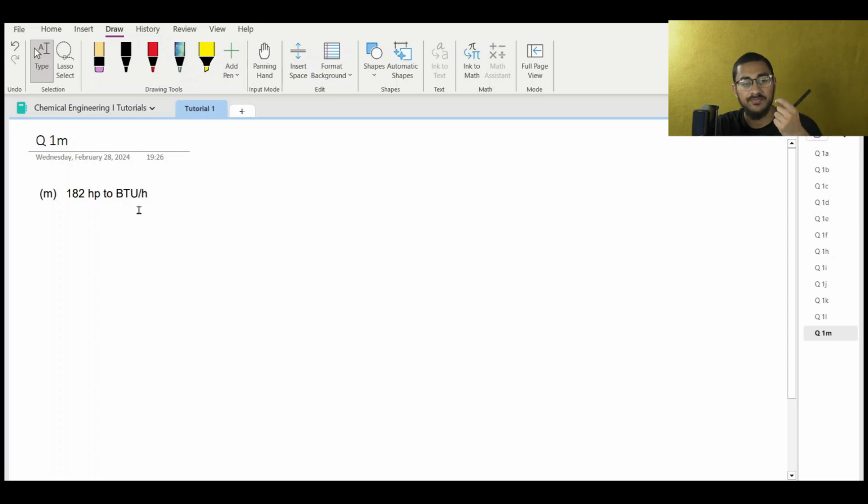If you go to your datasheet, you don't have information on the base units for horsepower. So my recommendation is going to be, turn that horsepower into something you understand. Bring it back to the metric system where you have an appreciation for how the numbers and the units work. And from there, let's move it into BTUs per hour. All right. So let's start off doing that.